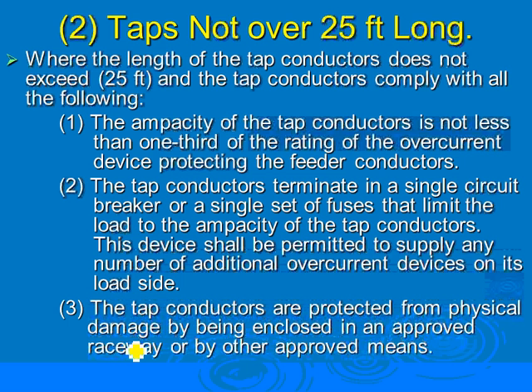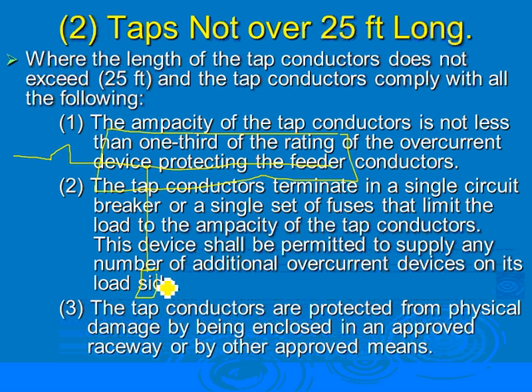Okay, let's go to 25 feet. 25 feet is even easier. 25 feet, guys. Here's my conductor. Let's take the same conductor. Can you guys see the color here? Okay, so let's go tap it. And that's a poor man's job, when I don't pay for the cover, so probably that's a problem when you don't pay for things. So here's your fuse, here's my disconnect inside it, and here's my equipment, machine, panel, you name it. The distance here, from here to the conductors, let's be very specific here, is 25 feet.